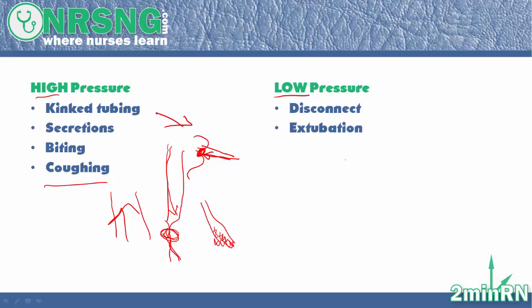Now let's talk low pressure. The ventilator is trying to push oxygen in and it senses that there is no pressure — it doesn't have any effort that it's trying to work against. The primary cause is going to be disconnection. The tube becomes disconnected from the ventilator, or where the tube goes into the patient's mouth there's a disconnection, so it's just blowing air straight out and not delivering it to the lungs.